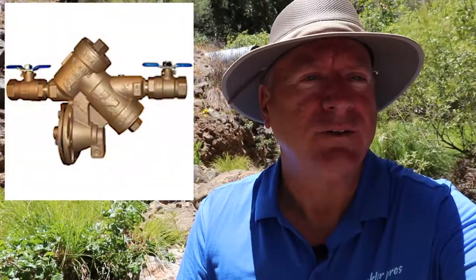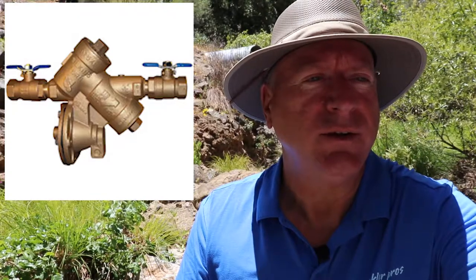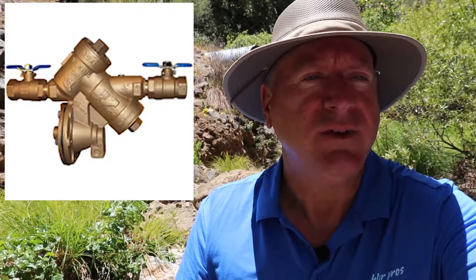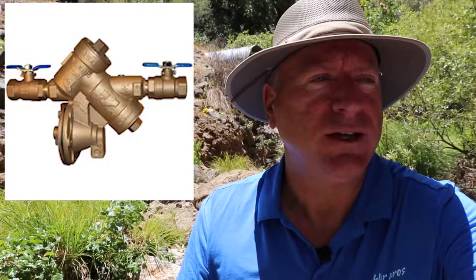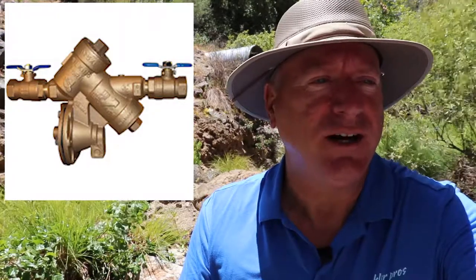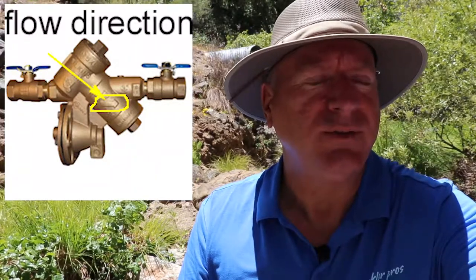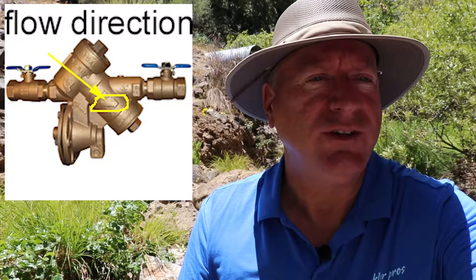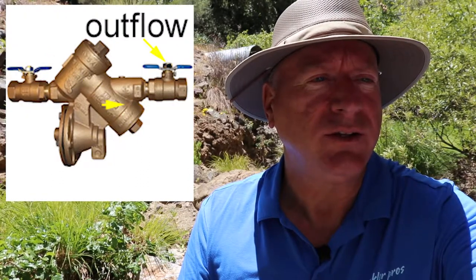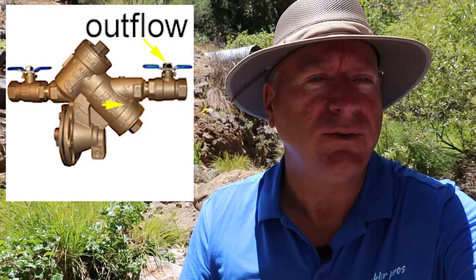You may have a shutoff valve already in the form of a backflow device. I'll go more in detail about backflow devices in another video, but suffice to say if you have a backflow device it will look like one of these that you see in this photo, and it needs to be turned off in a certain manner. Look for the flow arrow imprinted on the backflow device here. Once you see the flow direction, know that the correct shutoff valve to shut off the system is the outflow valve.